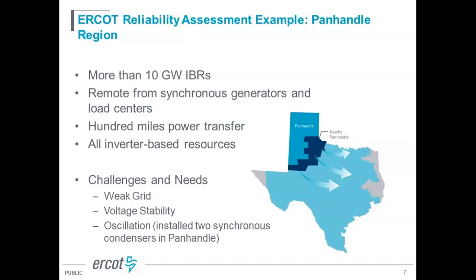And this area is far away and remote from the synchronous generators and load center, which are typically in the central part and the coastal part of Texas. So from this perspective, if we look at the Panhandle region only, it's really 100% inverters, and they need to transfer power over 100 miles to the load center in the central and coastal areas of Texas. So from that perspective, focusing on that region, it is really 100% penetration.